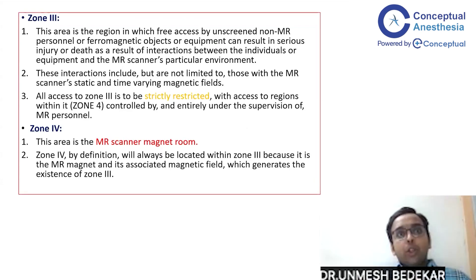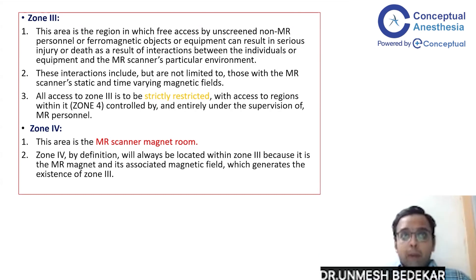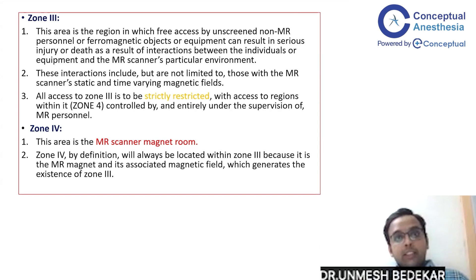Zone 3 is the region where free access by unscreened non-MR personnel or ferromagnetic substances can result in serious injury and even death due to interactions with the MR scanner's static and time-varying magnetic fields. This zone is strictly restricted and entirely supervised by MR personnel. Zone 4 is the main MR scanner magnet room, which is always located within Zone 3, because it is the MR magnet itself and its associated magnetic field that generates the existence of Zone 3.